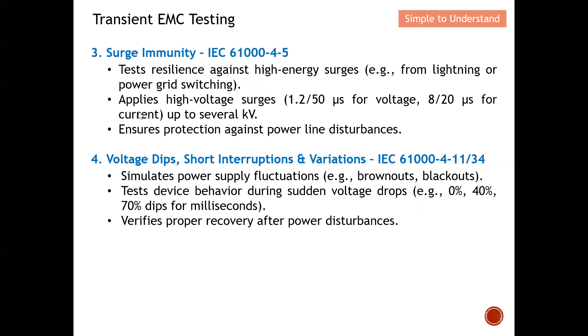We also have surge immunity. The key purpose is to test your DUT's resilience against high-energy surges, for example from lightning striking nearby or power grid disturbances. We apply a very high voltage surge of very short duration — it can be up to several kilovolts — to ensure we have proper protection against power line disturbances.